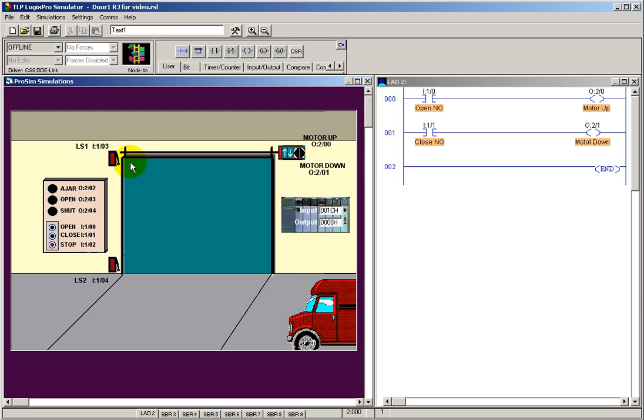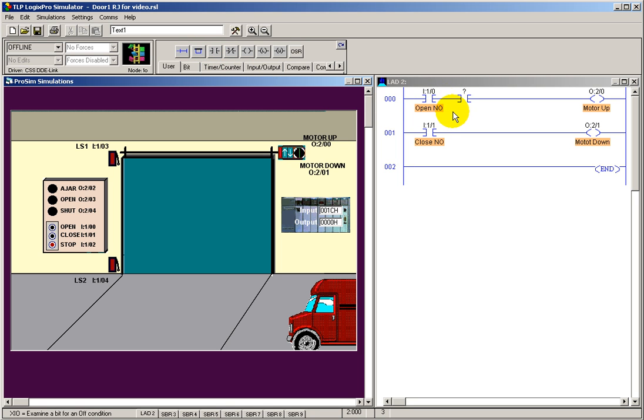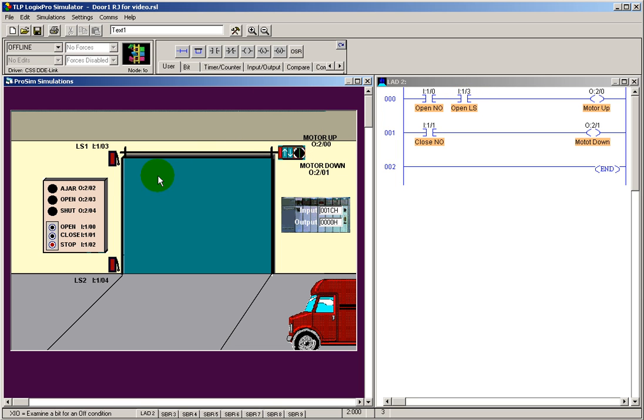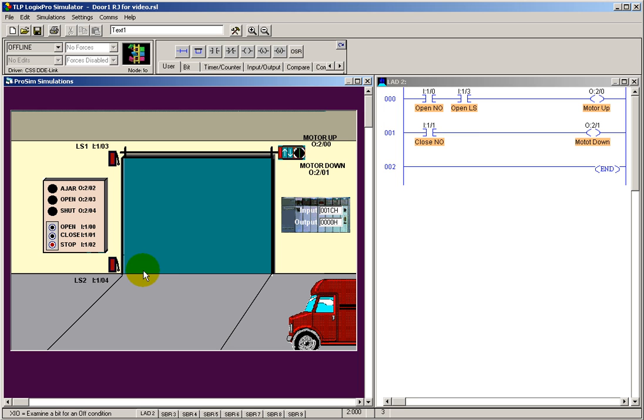So for that reason, we're going to use two different instruction sets. In rung one, we don't want to over travel. We don't want to open this up beyond fully open. So we're going to put an instruction set here as examine if closed for the open limit switch. Let's bring an open limit switch address over here. So this is open limit switch. What this is saying is that I can open up as long as this guy is examine if closed. And it is closed when it's anything but open. This switch is closed if it's anything but fully open, the door fully open. That sounds a little confusing, but think about it again. This guy is always activated as long as it's even an inch down all the way to being fully closed.